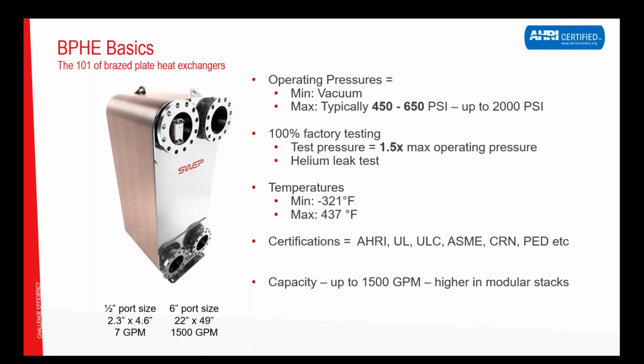I would like to say here that copper is the most common. The plates are made of stainless steel, but they are bonded together by copper. SWEP also has an all stainless range with plates and bonding material in stainless steel that has higher temperatures. But since copper brazed heat exchangers are more common for energy recovery, that is what I'm focusing on today. Please contact SWEP if you want more information about brazed plates or all stainless bonded heat exchangers.